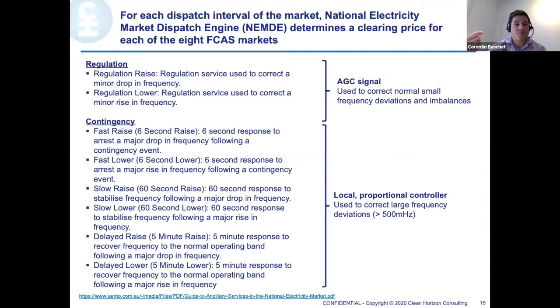Regulation is not a symmetric service - you've got a raise service and a lower service to go up and down to correct frequency deviations. These regulation signals are based on an AGC signal, whereas contingency is based on the frequency measured at the site. So the battery storage system will not receive an AGC signal from the dispatch center - it will simply be operated based on the frequency it measures on the network.